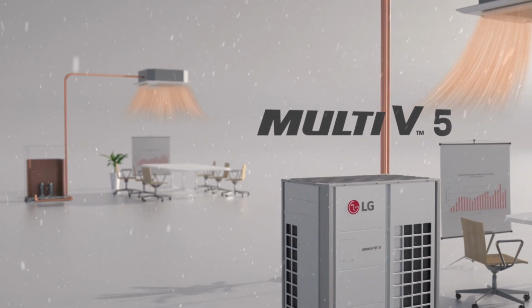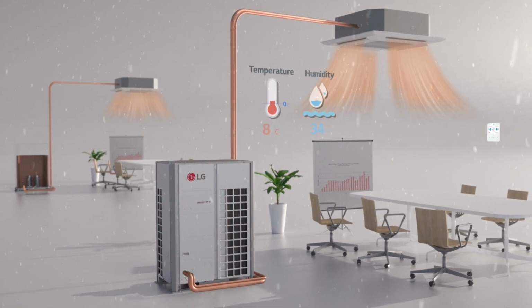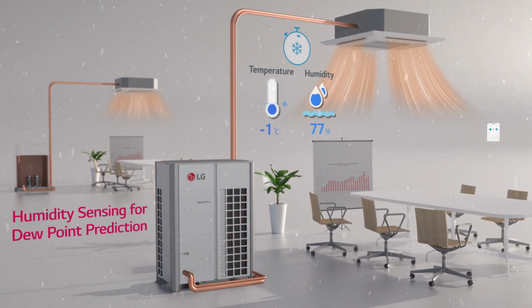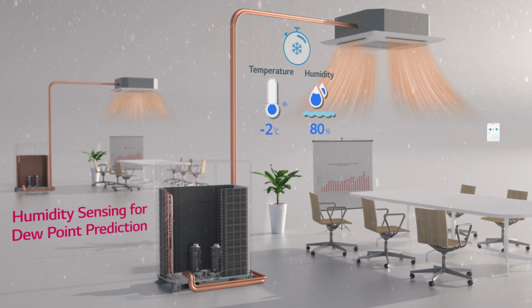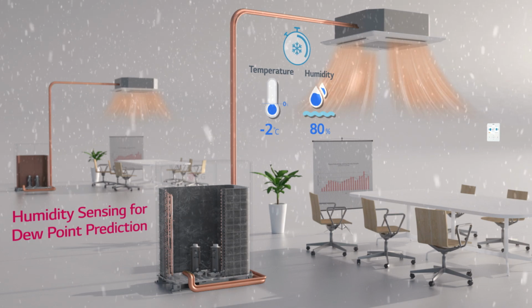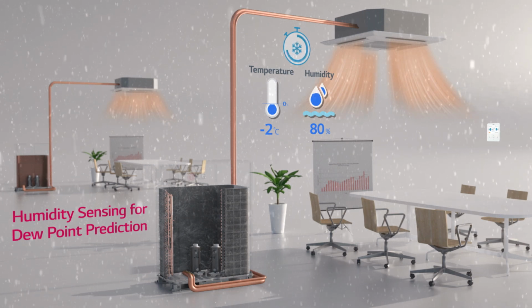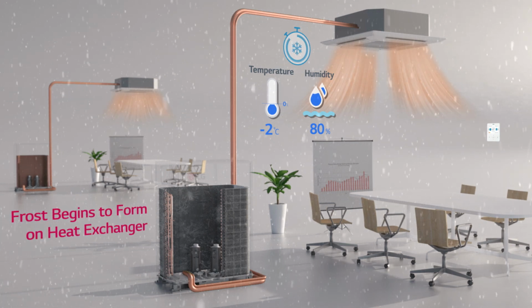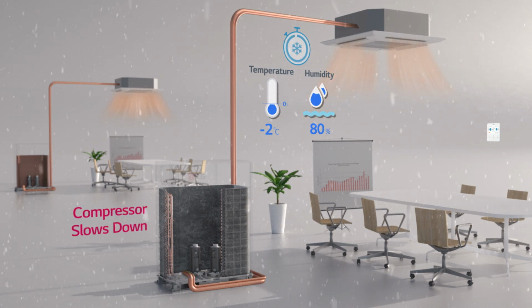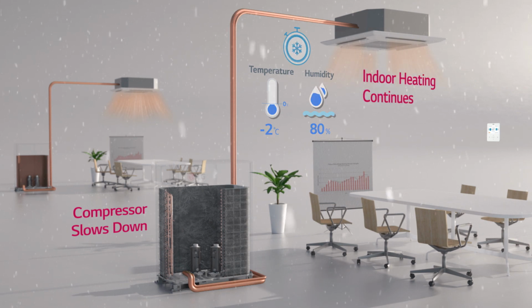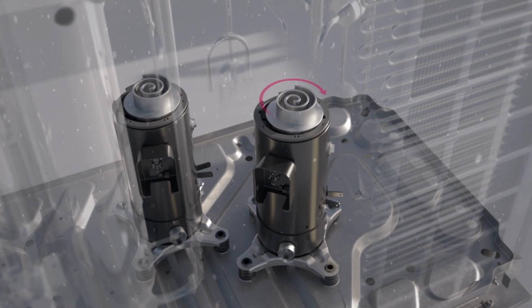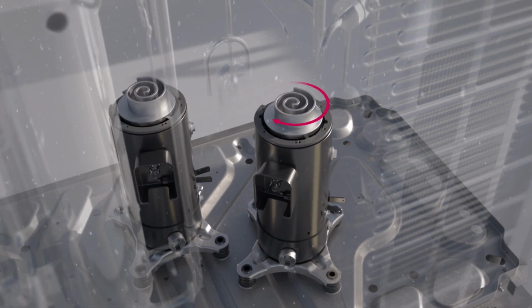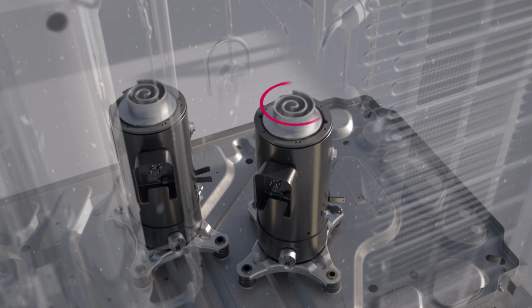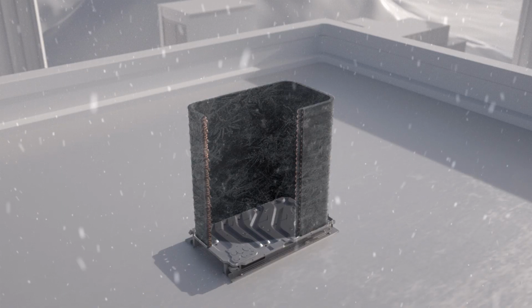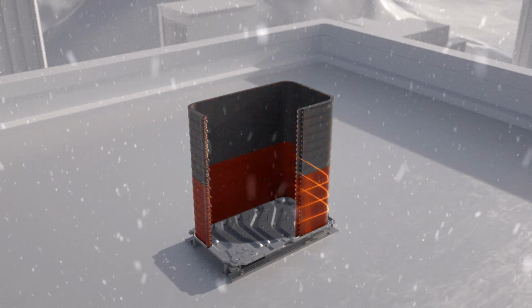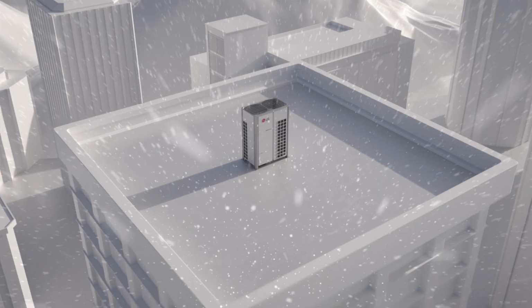However, thanks to the Multi-V5 with dual sensing control, this is no longer a problem. By sensing humidity, accurate prediction of the dew point is possible, enabling the Multi-V5 to autonomously control heating operation in order to delay the freezing moment. Look how smart it is when sensing the humidity. When frost forms up on the four-sided heat exchanger, the compressor slows down in order to delay frosting. Accordingly, the indoor heating performance slightly decreases, yet it continues to keep the indoor space warm. By the time that defrosting is necessary, the heat exchanger runs a partial defrost to quickly and effectively defrost the outdoor unit and return to heat production for the indoor space.